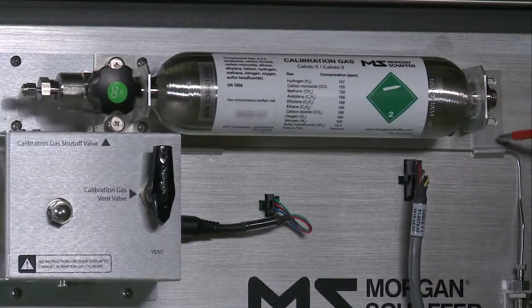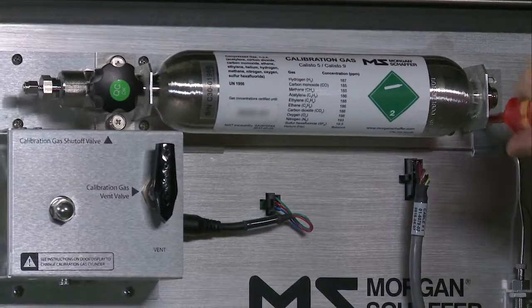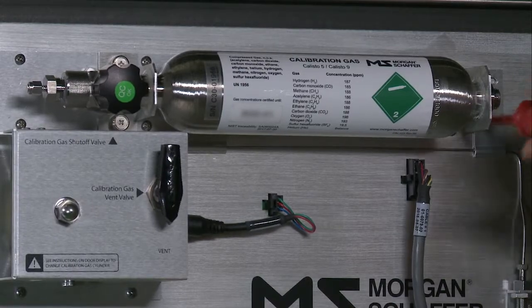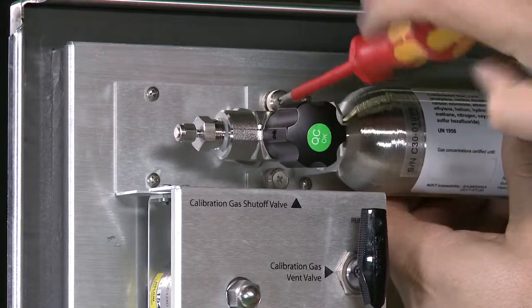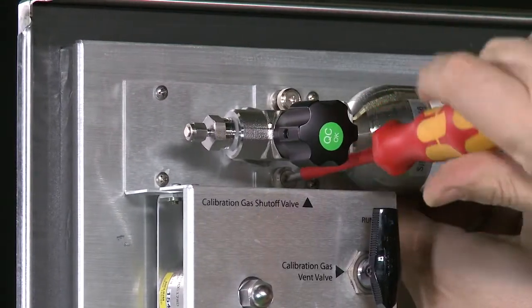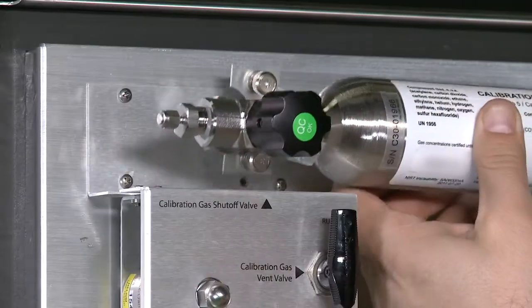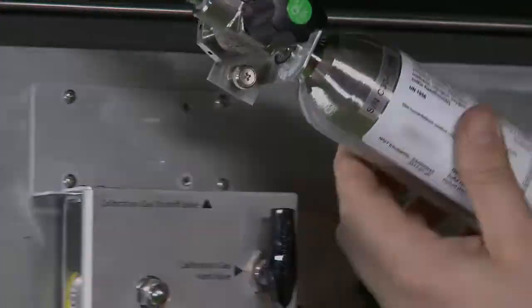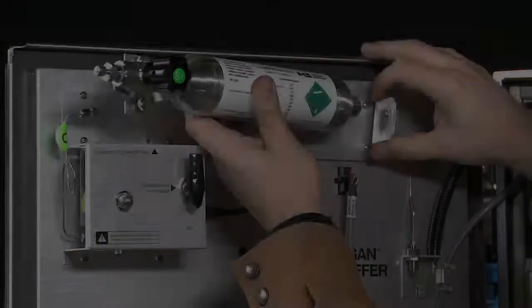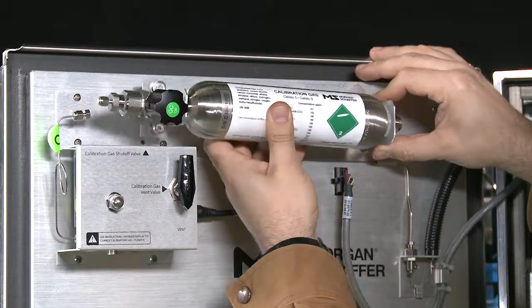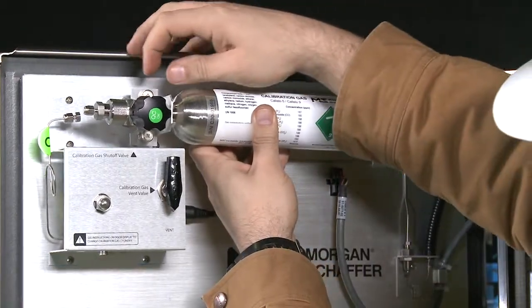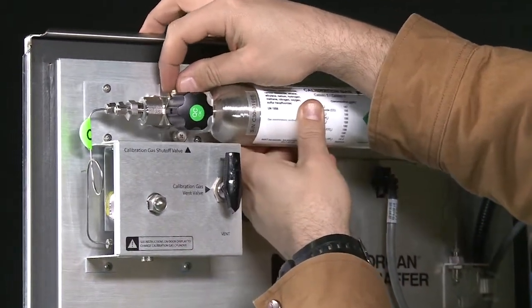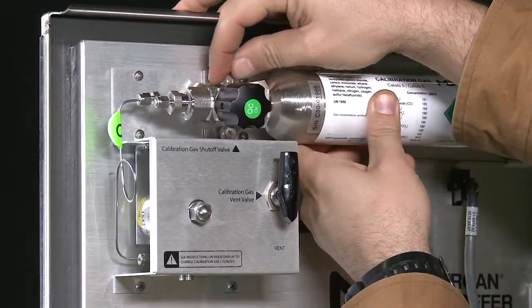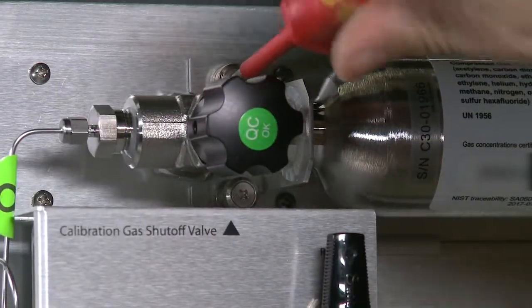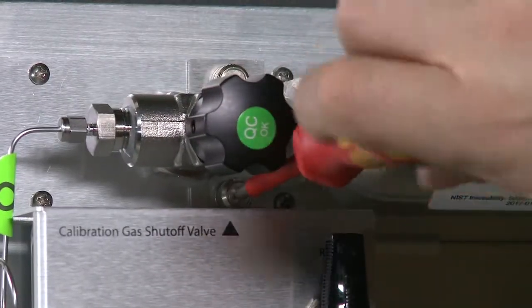Using a Phillips No. 2 screwdriver, loosen the 2 screws of the cylinder retainer. Loosen the 2 Phillips screws on either side of the shutoff valve and remove the calibration gas cylinder. Installing the calibration gas cylinder. Install the cylinder by inserting the bottom of it into the retainer first, then turning the 2 captive screws by hand and tightening using a Phillips No. 2 screwdriver.